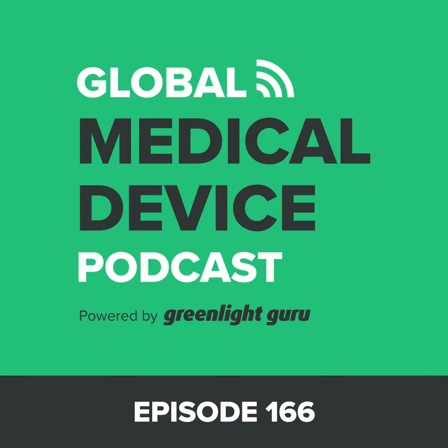Even in one of the companies that I'm working with right now, we're putting together a pre-sub. They're using silicone in their particular medical device, and they're trying to make an argument that, yeah, people have been using silicone for a long time for different things, but the problem is there's different kinds of silicone, and they don't always act the same way. And the challenge for us as manufacturers is the material suppliers that we're getting our materials from are usually not going to be keen on telling us, oh yeah, this exact formulation of this material is something that we sell to your competitor to make some other medical device.